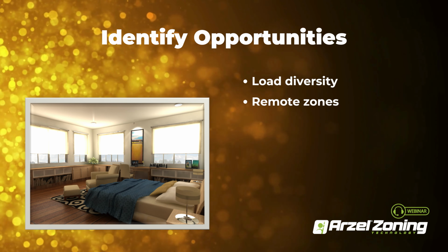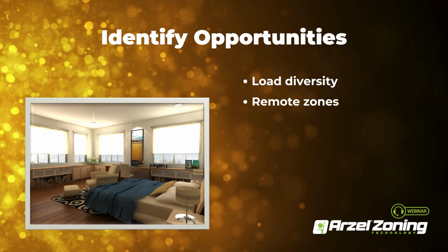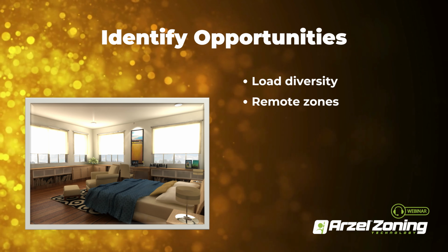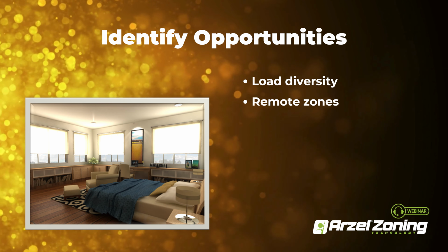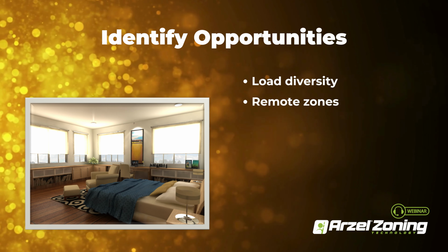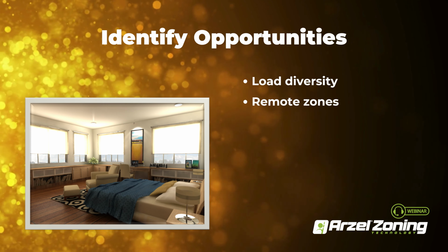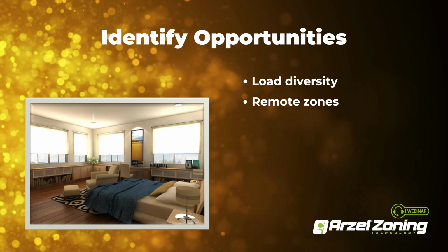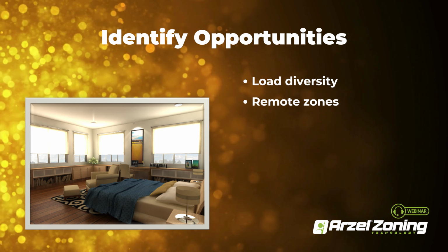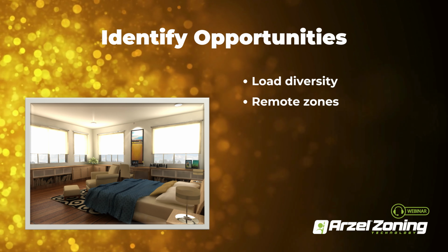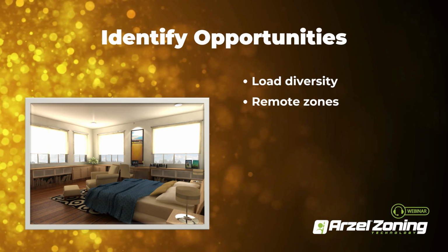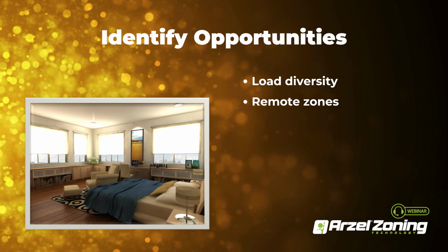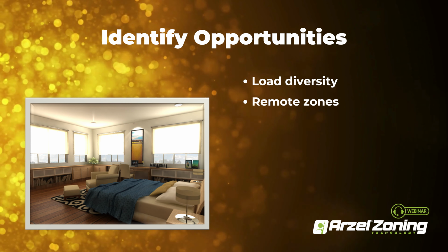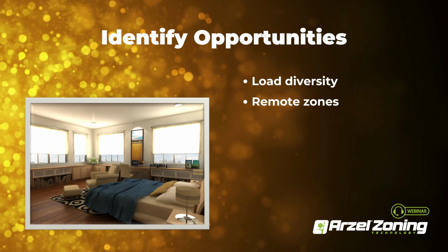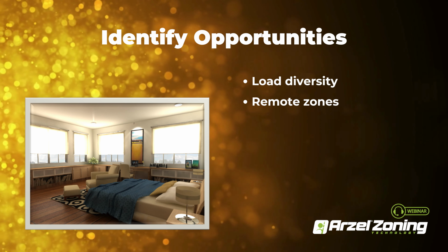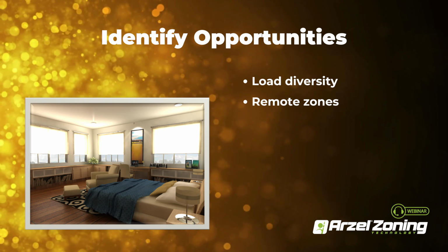We've got remote zones. Bonus rooms over the garage are very popular with a lot of homes today, and a lot of times the ductwork's run there but isn't finished, just run into that area and capped off. Oftentimes the equipment itself isn't sized to handle that additional load. So if we have a remote zone like that, we don't necessarily have to replace the equipment to upsize it for that area. We can zone that off, and as we direct the BTUs from other parts of the home that don't necessarily need it, we can effectively condition those areas that are in remote locations.